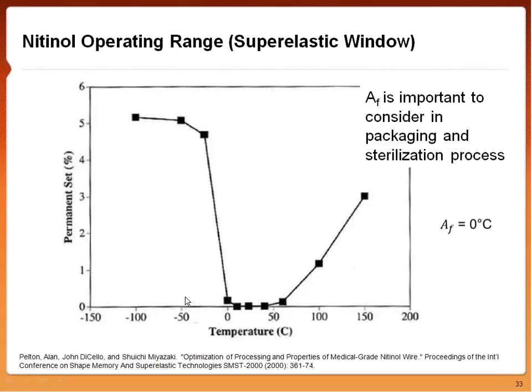But if you think about it, based on those earlier curves, by shifting your AF, you can shift how stiff your device is. When you shift your AF, you also shift this window. So if you imagine a customer says, okay, I want an AF of maybe minus 20 degrees because I want a super stiff stent, you're going to shift that window down, and you might actually hurt your device when you go to sterilize it, which isn't good. So you're going to have permanent set in your device when you go to sterilize it. So those are things you have to keep in mind, that nitinol really only operates superelastically over a given range of temperatures. And you can determine that just by testing and figuring that out yourself. Again, superelastic window.